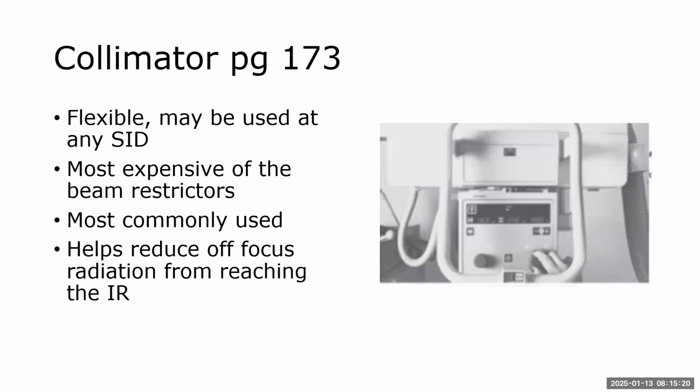Do y'all know what off focus radiation is at this point? We might have talked about it just a smidge last semester. Off focus is that radiation that is created somewhere besides at the target in the tube. So we don't like that radiation, right? We want that radiation that's created at the target and comes down as primary, exits the window, and is directed at the patient. And so there's a video, let's see if that's for next week in your Rad Tech Bootcamp, about off focus. It's very short, but it'll help you understand that a little better.